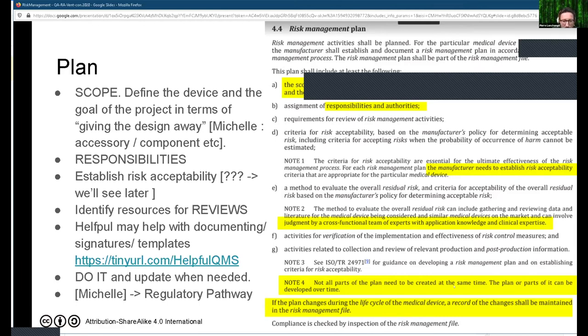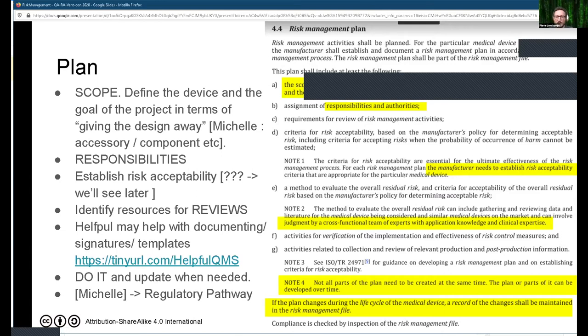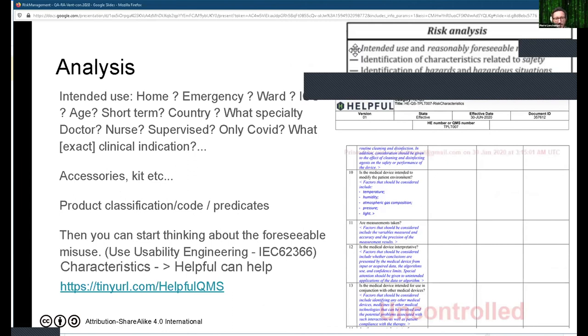You can join us on the Helpful Engineering QMS, where we have resources to help you write this plan, including electronic signatures. The first step after planning is to analyze — to identify all the hazards and hazardous situations. To do that properly, you need to further define your intended use, whether you are developing accessories, and classify your product.